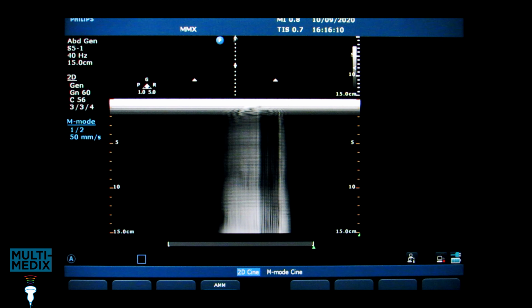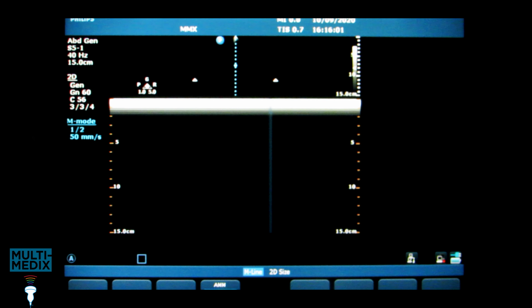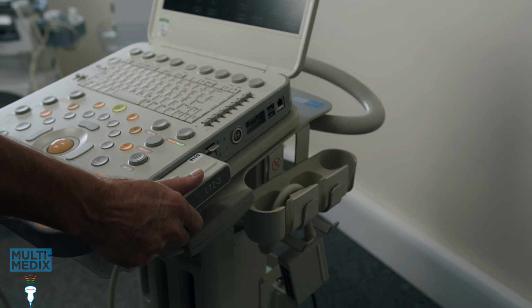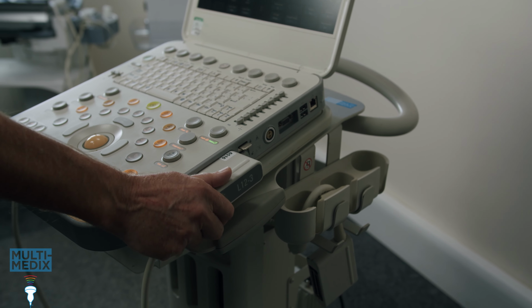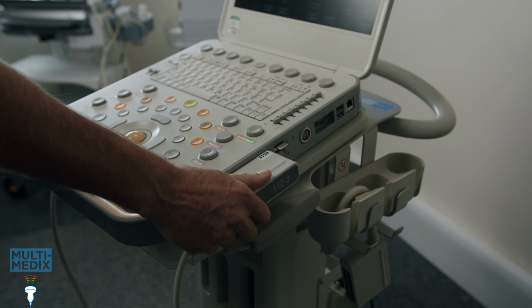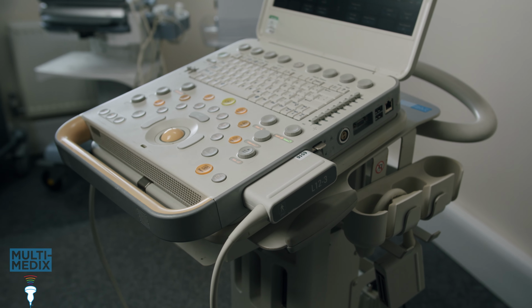If there's dropout, it's important to check it's not due to the connector or port, so wiggle the connector, move it to another port if you need to. Connectors can get dirty, so cleaning with compressed air might resolve the problem. If the defect is still there, it's associated with the probe, which should be rejected. This all works for conventional probes.